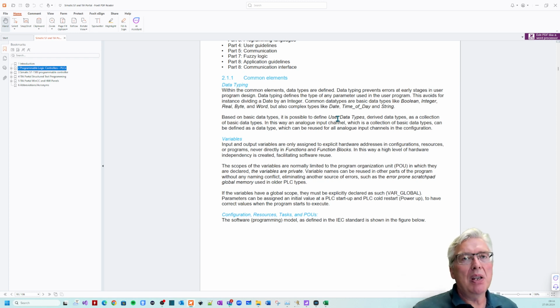A typical one would be, for instance, a floating point number and a quality code as a word. A word is 16 bits. That could be a structure if you want that. Because when you do processing and data is flowing through your application, of course you need to transmit a quality code along with the data, so you know what you are looking at, if that's okay. You can have a structure, for instance, for a 64-bit floating point number with a quality code. It doesn't have to be a word, it could basically be a boolean, because in automation it's either good or bad. You can't work on bad values.